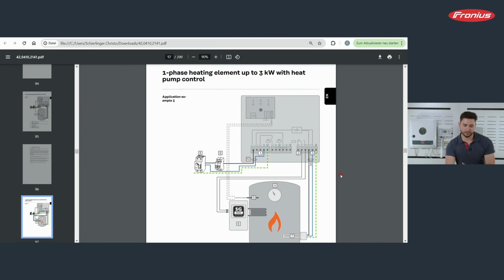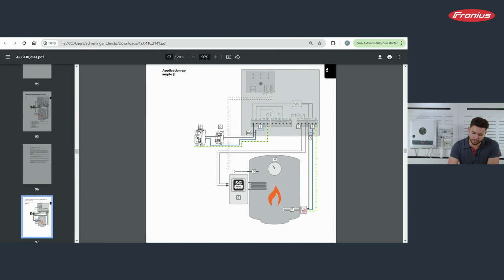Now, in this manual, we also have other examples, like we see here with the Smart Grid Ready. So here I can explain a little bit better what we have just seen in the Ohmpilot menu. We have a single phase heating rod connected in the boiler, and the multifunctional relay is being used for the control of this Smart Grid Ready heat pump. And the signal only switches to on when we reach a certain threshold, like we have seen, 4 kilowatt or whatever, however big the heat pump actually is.